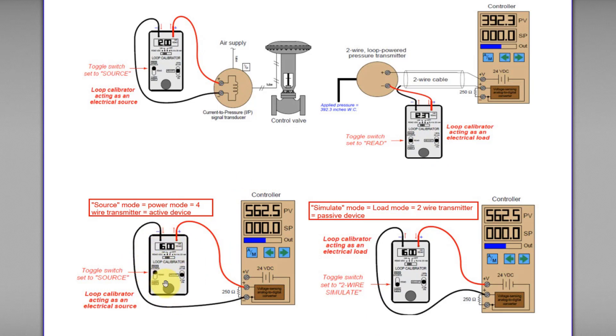This loop calibrator switch is set to source mode. As mentioned earlier, source mode will act as an electrical source — it will provide the power to power the whole loop, and at the same time inject a signal. So it is actually no different from a four-wire transmitter. Since this is the electrical source, the controller will act as an electrical load.